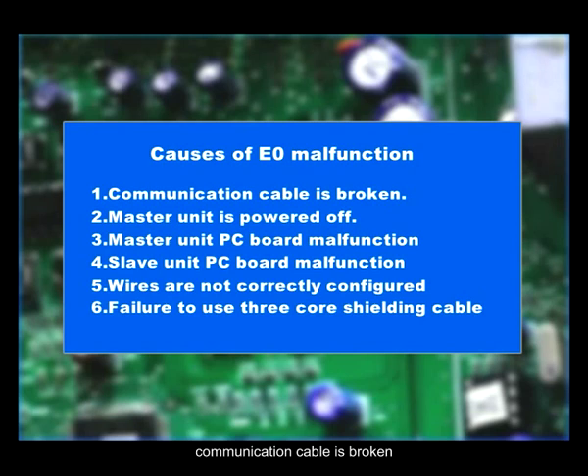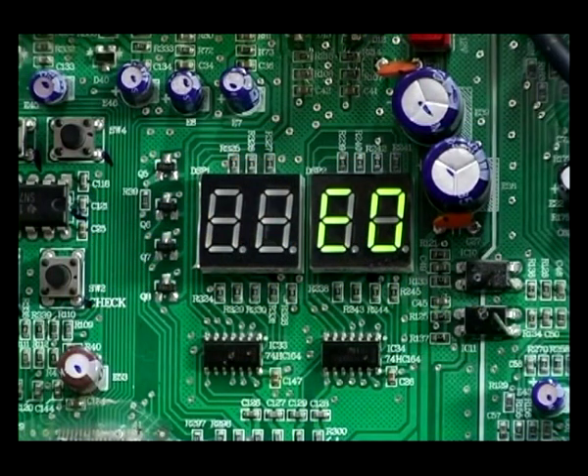Communication cable is broken. Master unit is powered off. Master unit PC board malfunction. Slave unit PC board malfunction. Wires are not correctly configured as per instructions. Failure to use 3 core shielding cable. Repair instructions when E0 appears.